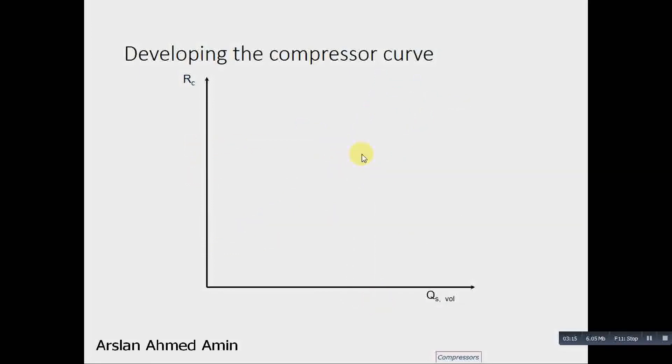So this is a compressor characteristic curve, and curves are shown at various speeds. This is the minimum speed and this is the maximum speed. And this is the surge limit, the minimum flow point. Where we want the flow to the right side of this line. We don't want the flow to cross this line because this will lead to damage.